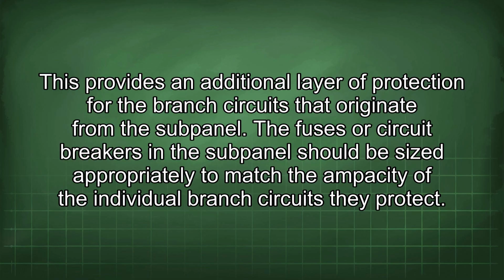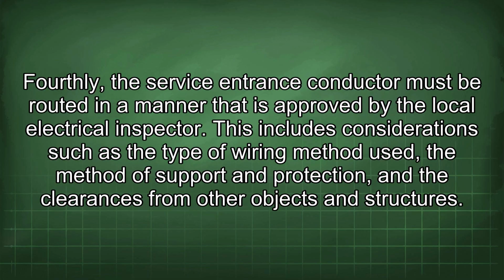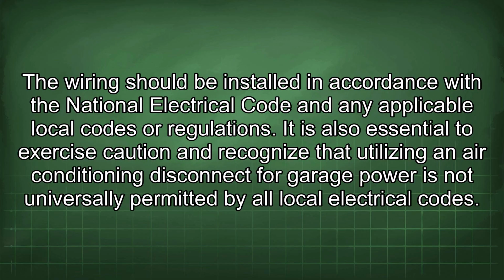Fourthly, the service entrance conductor must be routed in a manner that is approved by the local electrical inspector. This includes considerations such as the type of wiring method used, the method of support and protection, and the clearances from other objects and structures. The wiring should be installed in accordance with the National Electrical Code and any applicable local codes or regulations.